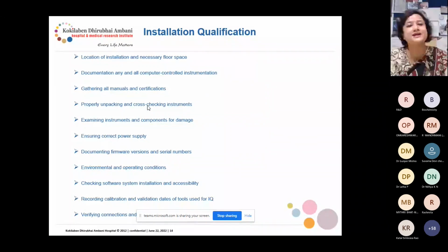Documentation for any and all computer-controlled instrumentation, gathering all manuals and certifications, properly unpacking and cross-checking the instruments, examining instruments and components for damage, ensuring correct power supply, documentation, firmware versions and serial numbers, environment and operating conditions, checking software system installation and accessibility, recording the calibration and validation date of tools used for IQ, and verifying all the connections. So all this should be there in the installation qualification report.